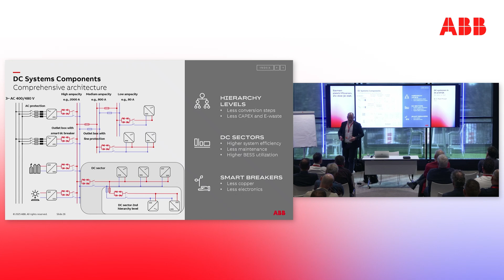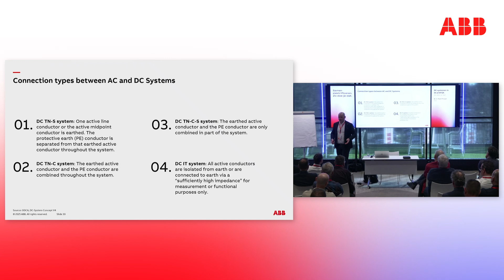If I have both AC and DC, how do I deal with the grounding topic? In principle, grounding of a DC system is not really different than grounding an AC system. We can think of probably the same four options: protective earth with the neutral combined or divided, grounding on the AC part, or leaving the DC system ungrounded. Spoiler alert, the last option is the most popular.